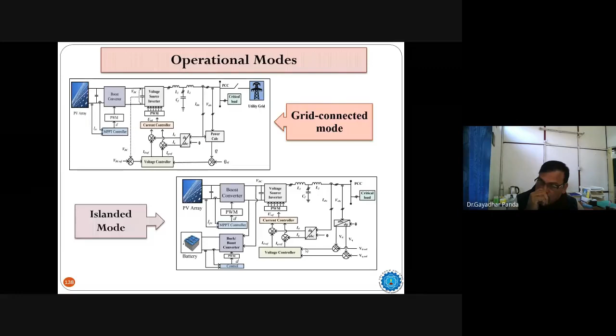Similarly, there may be a complication: the power generation available from PV, wind, or energy storage may not be sufficient to meet the load demand. Then there is a chance you have to go for load shedding also, meaning priority based load. Now we are segregating. When we are thinking of a microgrid system, you have to segregate the loads, priority based loads: which are the sensitive loads, and which loads can be disconnected easily. Those things you have to take into account when you are designing a microgrid system for seamless operation.